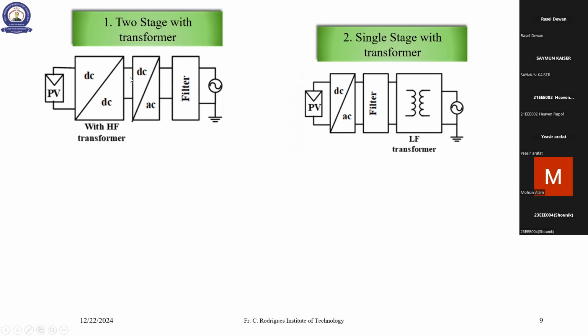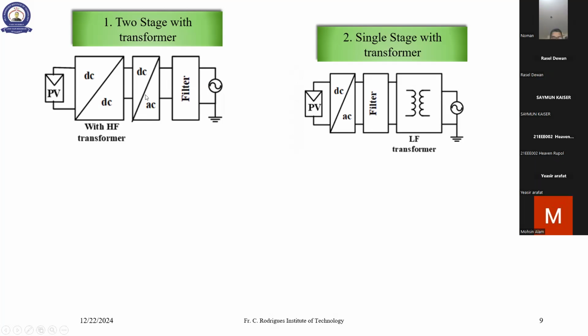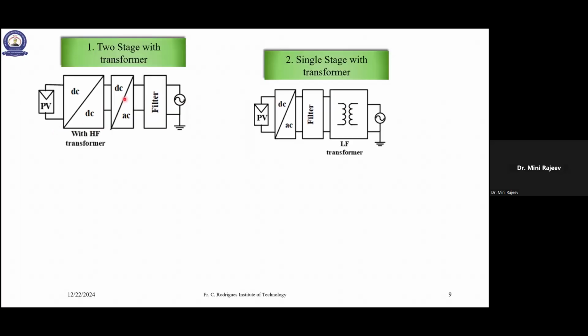Okay. And then the output of that will be given to an inverter. The inverter output is not pure sinusoidal, so you use a filter to filter out the high frequency components. And then it is given to the grid. There are two power conversion stages, so the efficiency will be lesser in this. But from the control point of view, it is better because you can control the DC to DC converter for the DC side and the DC to AC converter for the AC side independently.